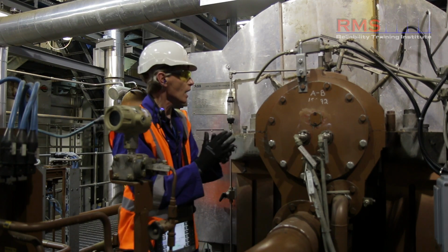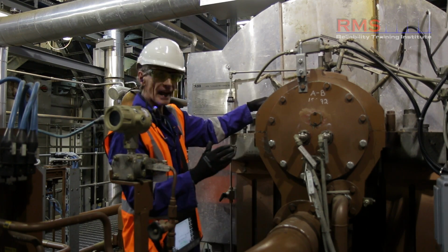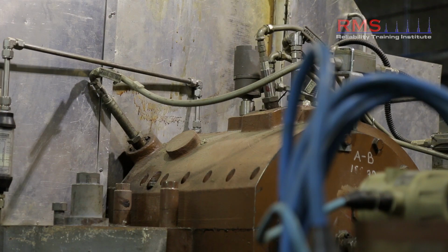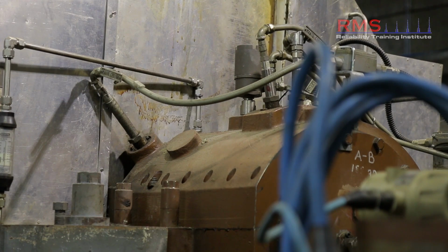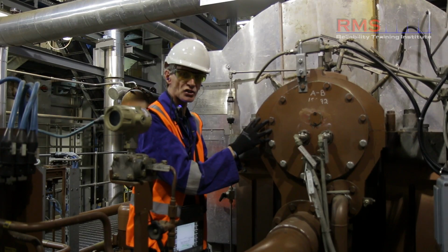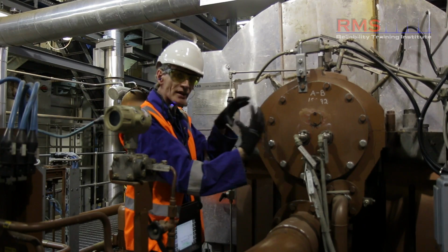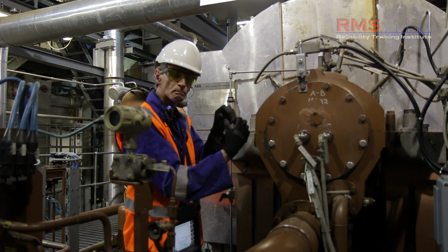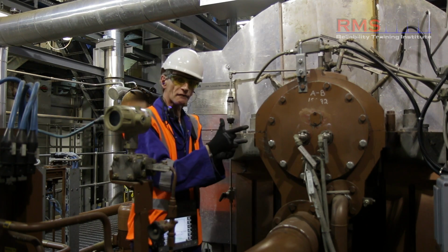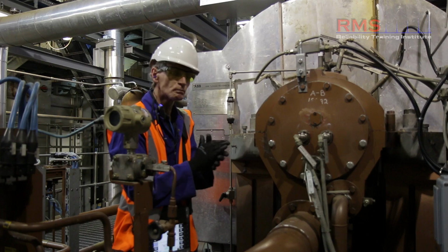people call them. We have X and Y probes looking at the gap between the probe tip and the actual shaft within the bearing itself. So it's measuring the movement of the shaft in free space. This shaft is running at 9,000 RPM.